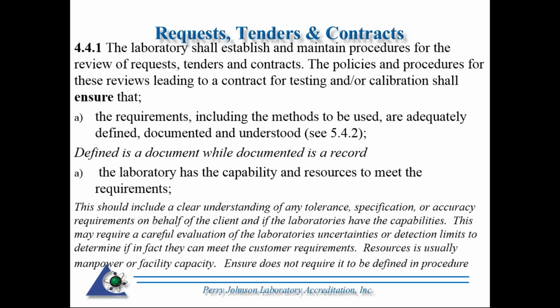These may require a careful evaluation of the laboratory's uncertainties or detection limits to determine if, in fact, they can meet the customer's requirements, i.e. they want something tested or calibrated to fall within a specific tolerance. The laboratory needs to assure that they have the capabilities to meet those tolerance or specification limits established by their clients.